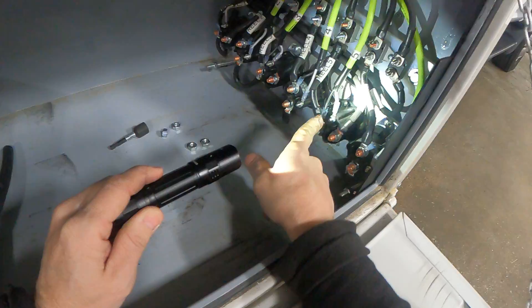So power comes in here, and these green wires are the switches on the hose reels that will power, or basically turn the reels on and off. When you push the push button on the reel, power comes out and then comes back in through the push button on this side. This is basically like a switched wire to tell this solenoid or relay to close and energize the circuit.